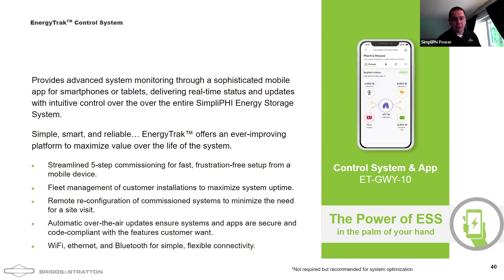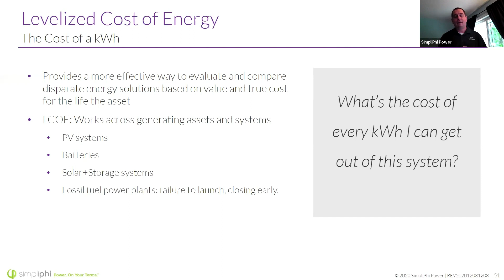Real quick, I want to talk about levelized cost of energy, because not all systems cost the same. When we talk about the cost of a kilowatt hour, we really want to talk about the cost of that kilowatt hour over the life of the system, because a similar lead acid bank might have a nameplate of a similar kilowatt hour, but if you're only taking it to 50% depth of discharge, you don't have the same usable energy. Further, over time, as that battery degrades, you're not going to get as many kilowatt hours out of it. So it's very important, if you're selling to the end user or creating the cost analysis, to understand that the levelized cost of energy of a lithium-ion system will be lower than a comparable system that may have a lower upfront price tag, but will have costs associated with maintenance, with replacing the system, with ancillary costs like fire suppression and heat sensors.